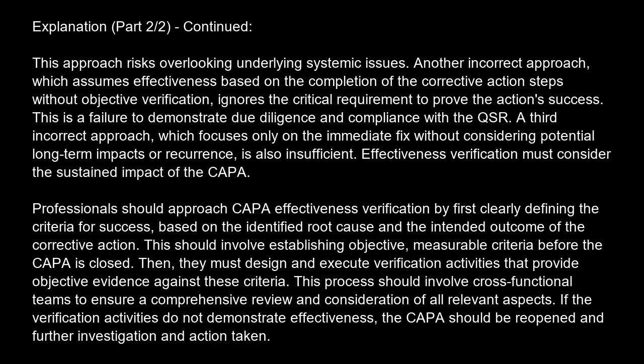Then, they must design and execute verification activities that provide objective evidence against these criteria. This process should involve cross-functional teams to ensure a comprehensive review and consideration of all relevant aspects. If the verification activities do not demonstrate effectiveness, the CAPA should be reopened and further investigation and action taken.